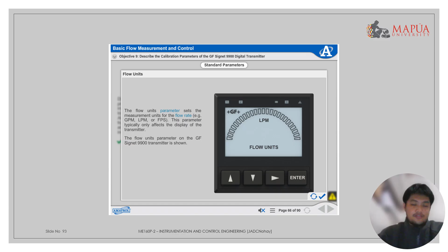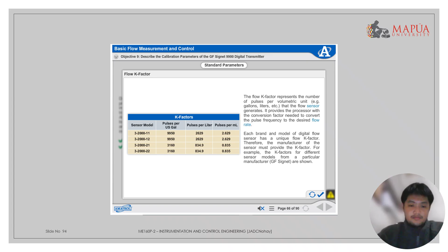The flow K factor represents the number of pulses per volumetric unit that the flow sensor generates. It provides the processor with the conversion factor needed to convert the pulse frequency to the desired flow rate. Each brand and model of digital flow sensor has a unique flow K factor. Therefore, the manufacturer of the sensor must provide the K factor. For example, the K factors for different sensor models from a particular manufacturer are shown.